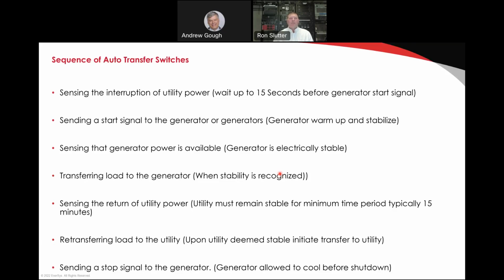Once we get past the 15 seconds, we send a start signal from the ATS to the generator, and we let it warm up and stabilize. Once the ATS senses that the generator power is good and electrically stable, we transfer the load to the generator. So once we transfer to the generator, we've been on generator for some period of time and the generator's running fine. All of a sudden, the utility power comes back.